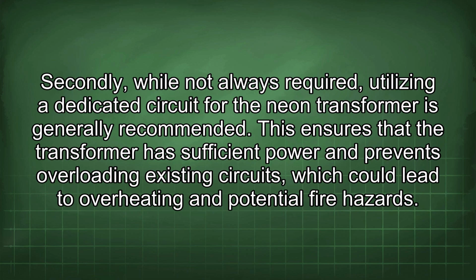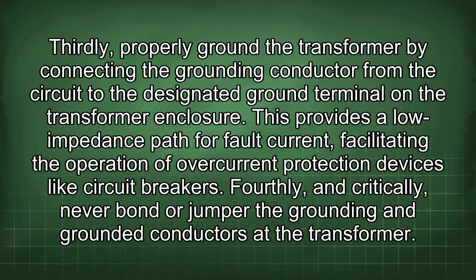Secondly, while not always required, utilizing a dedicated circuit for the neon transformer is generally recommended. This ensures that the transformer has sufficient power and prevents overloading existing circuits, which could lead to overheating and potential fire hazards.